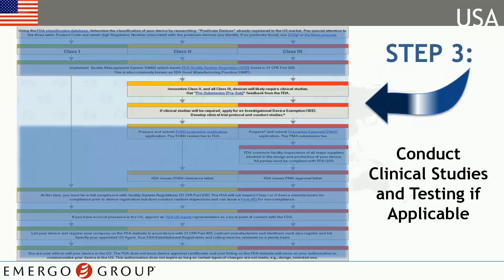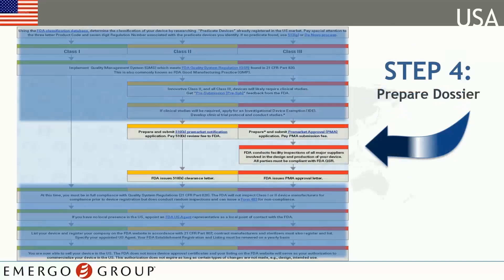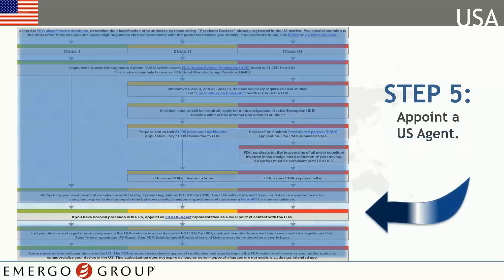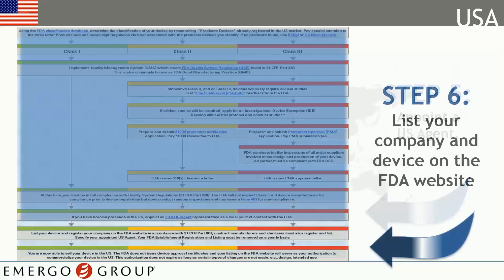Higher risk devices require clinical studies to be performed. Class II devices require the submission of a 510(k) pre-market notification application. Class III devices must submit a pre-market approval application, or PMA. If your organization is located outside the United States, you're required to appoint a U.S. agent as your liaison to the FDA. The final step is listing your device and registering your company on FDA's website.